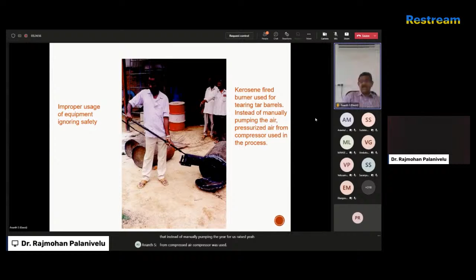This is one of the accidents that occurred due to misuse of pressure vessels. Here they were using a kerosene-fired burner for clearing tar barrels. Instead of manually pumping air, pressurized air from a compressor was used. This small tank had kerosene poured into it, and manual pumping was normally used to mix fuel and kerosene to establish the flame at the burner end. But instead of manual pumping, they used compressed air at a pressure of 7 kg per centimeter square.